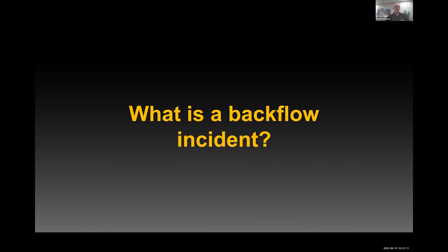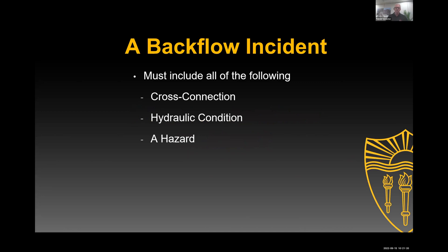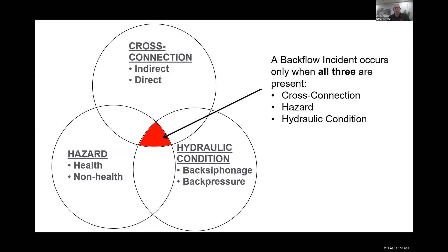No, not really an incident. The hydraulic condition is set up, but when we look at a backflow incident, that means something had to happen. There's a cross connection. In the case of my bathroom sink, there wasn't a cross connection because there was an air gap. There was a hydraulic condition — back siphonage was occurring. And there needs to be a hazard. So if there's a cross connection, a hydraulic condition, and a hazard, then that's a backflow incident — meaning that hazard got pulled into the drinking water supply.